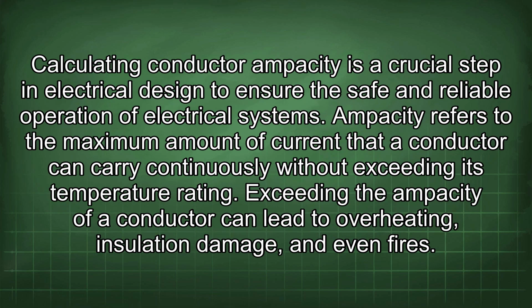Calculating conductor ampacity is a crucial step in electrical design to ensure the safe and reliable operation of electrical systems. Ampacity refers to the maximum amount of current that a conductor can carry continuously without exceeding its temperature rating. Exceeding the ampacity of a conductor can lead to overheating, insulation damage, and even fires.